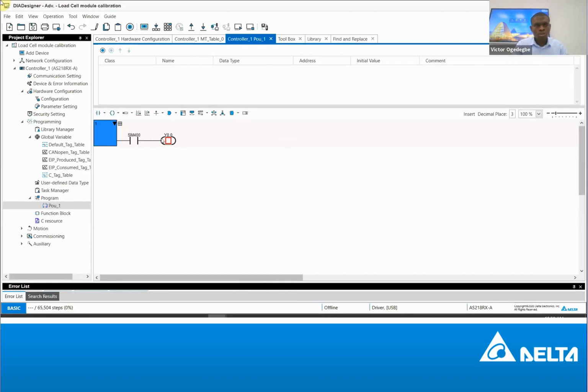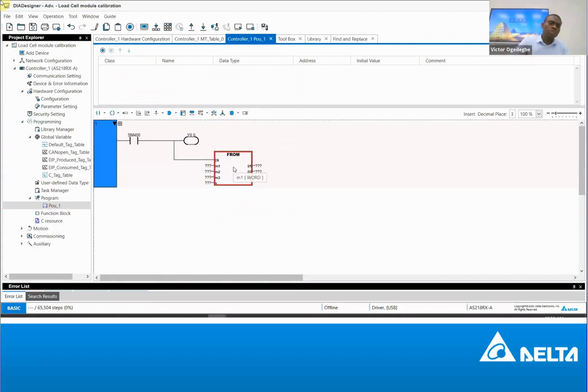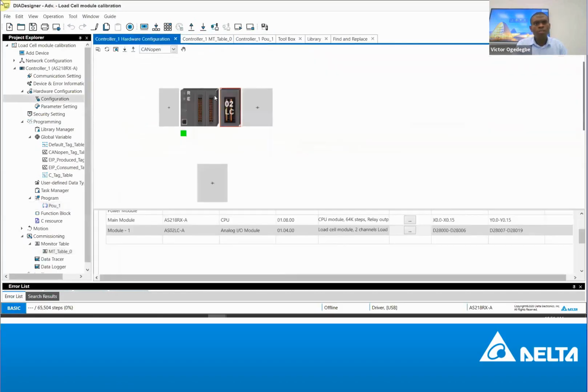And that was the first way, the TO instruction. There's also another instruction, FROM, similar to that one. If I click here, I just write FROM, F-R-O-M, enter. So it posts it there. What this does is read from the module. Maybe you need to read the measurement, some value. You use this instruction to read, and then you have the value that is in the module coming from this sensor, the weight sensor that is measuring some measurements in your application. TO and FROM. And then if you go back to, I already opened it before, the configuration itself.